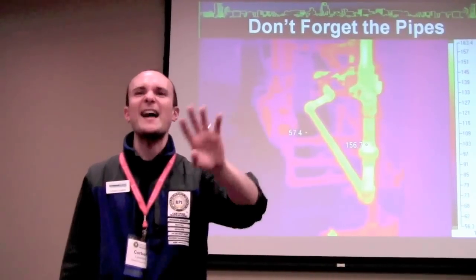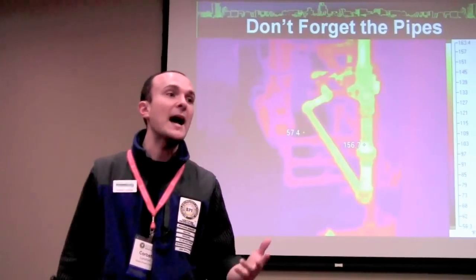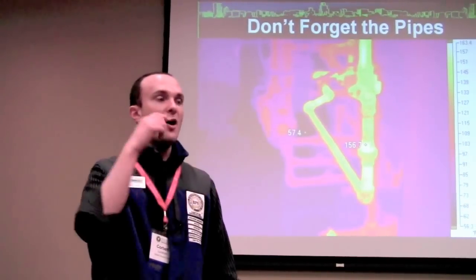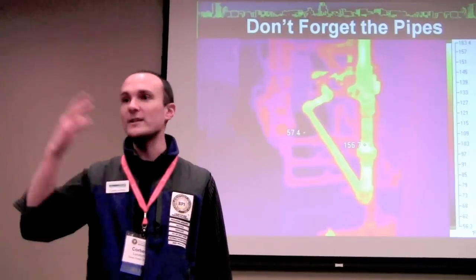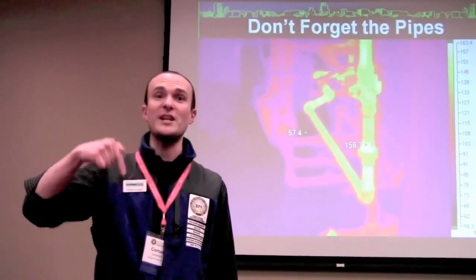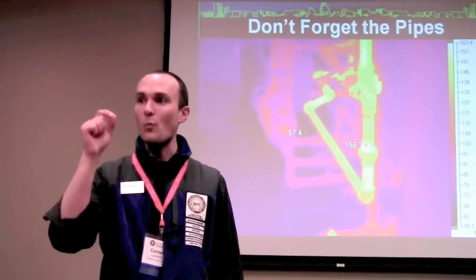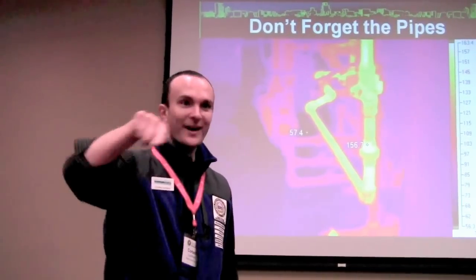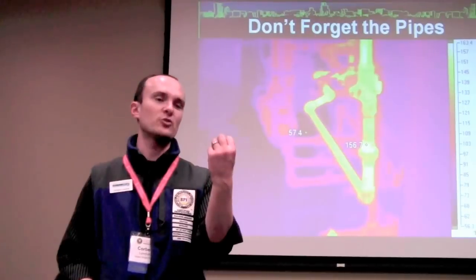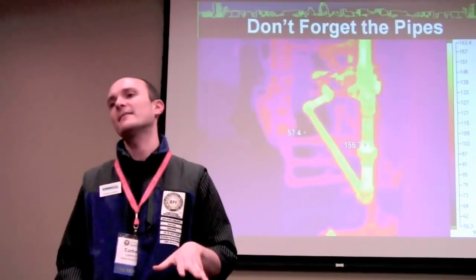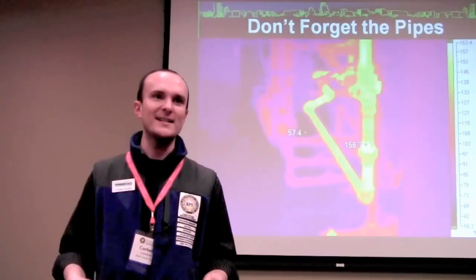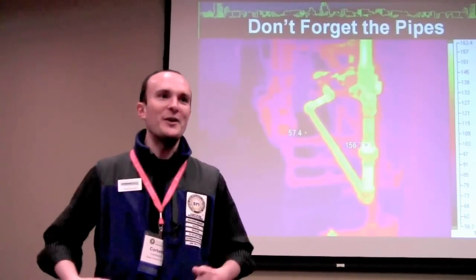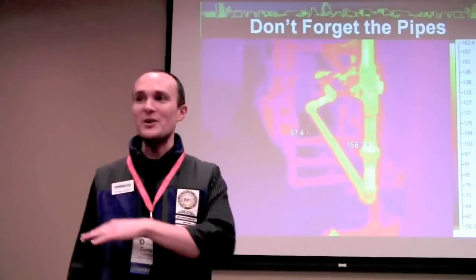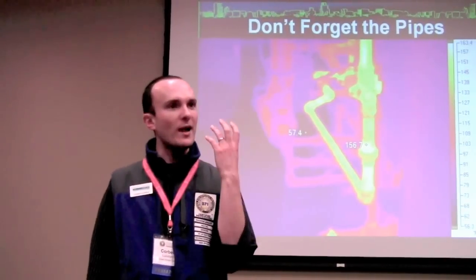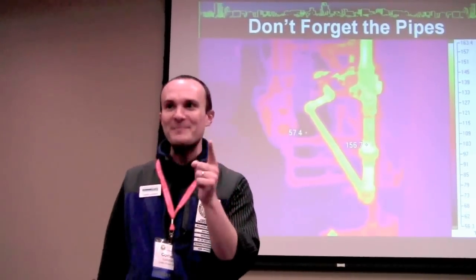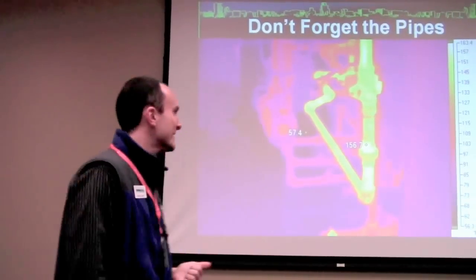As Mark would say, there's a guy who's going to fix that at some point. There isn't, it's you. That's why I always recommend insulating all pipes and ducts, even if they're in conditioned space, because if I'm going to engineer this system carefully, I want the water or air to go where I wanted it to go. That's ultimate control over the system. Think about it like your body: if you've got uncontrolled events going on inside, particularly in your intestinal system, that's really uncomfortable. Who wants that? No one. So we take lots of steps to make sure that never happens inside our body, but we don't pay attention to our houses the same way.